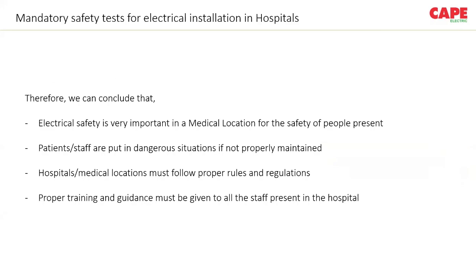For that, we will have to mandatorily follow the hospital or medical location rules and regulations. Electrical safety is very important, because patients and staff are put in direct danger if it is not properly maintained, since they are always in contact with the medical equipment. So proper training and guidance should be given to the staff to work the machines properly. And proper maintenance of the medical equipment has to be done every time, so that no electrical hazard can happen and no patient or staff is put in a danger where they cannot be rescued.